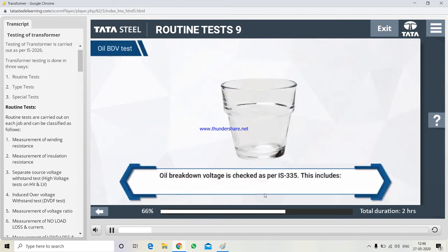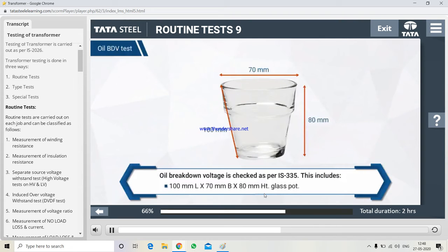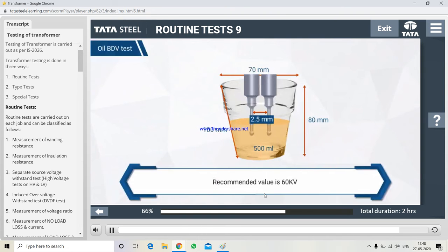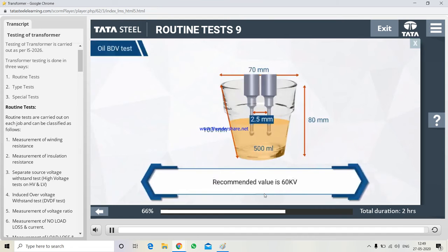Oil breakdown voltage is checked as per IS-335. This includes 100 mm length into 70 mm breadth into 80 mm height glass pot, 500 milliliter oil sample, spherical electrodes with gap of 2.5 mm. Recommended value is 60 kV.